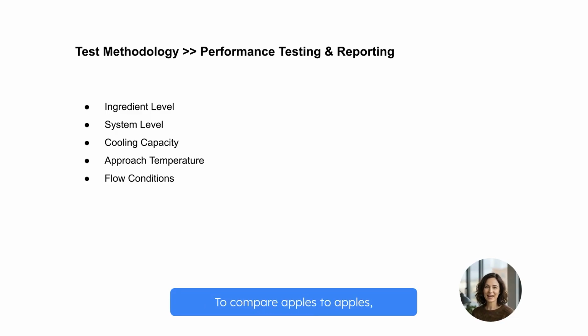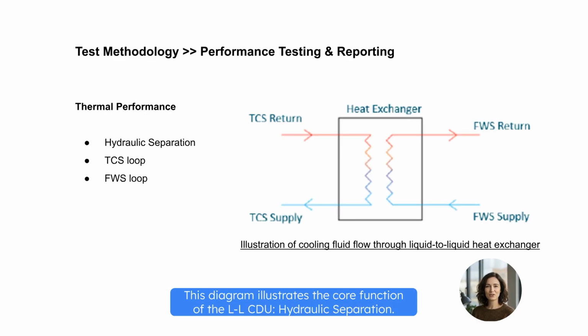To compare apples to apples, ignore the marketing fluff and lock in on these key metrics: cooling capacity, approach temperature, and the specific flow conditions for both FWS and TCS loops. This diagram illustrates the core function of the LLCDU hydraulic separation. On the left, you have the TCS loop collecting heat from the IT stack. On the right, the FWS loop rejects that heat to the facility.